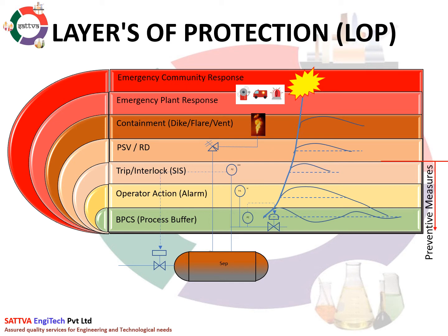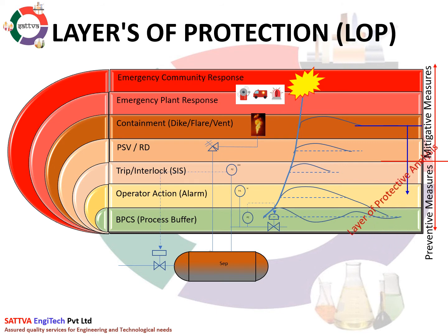In most cases, layers up to the safety instrumented system are typically considered as preventive measures, wherein the containment is not lost and most of these can be managed via proper engineering design. Mechanical protection and subsequent layers come under mitigation measures. Layer of protection analysis covers protection measures up to containment and reviews the effectiveness of these layers of protection.